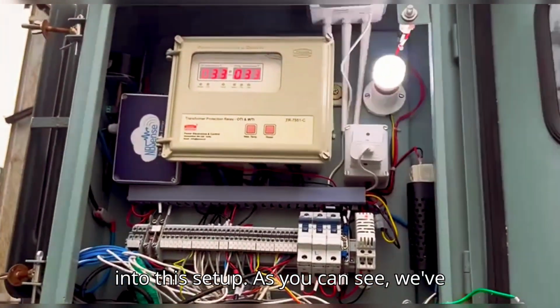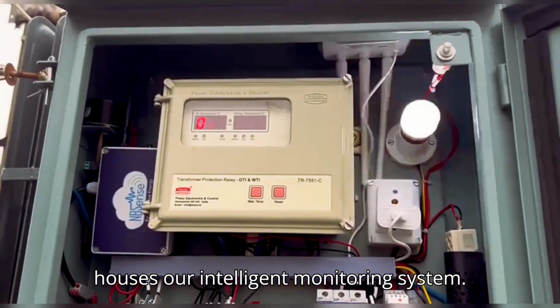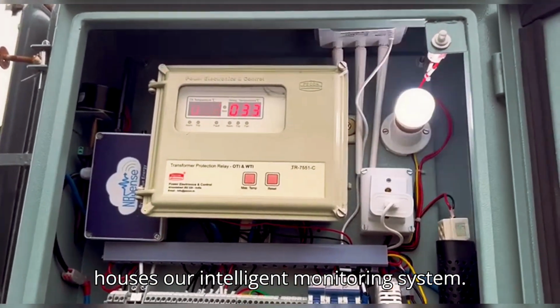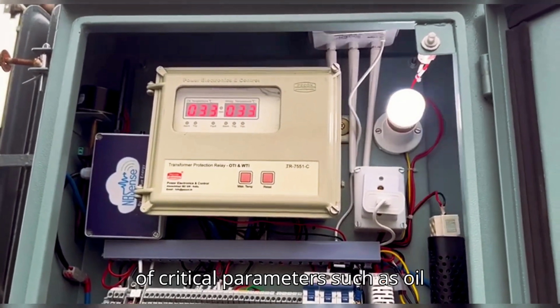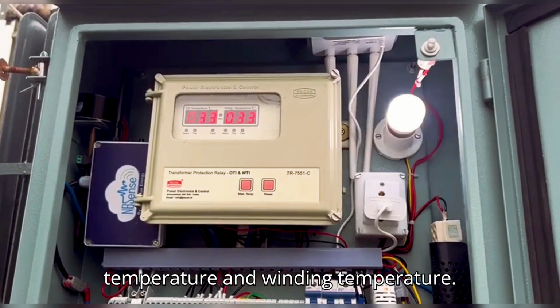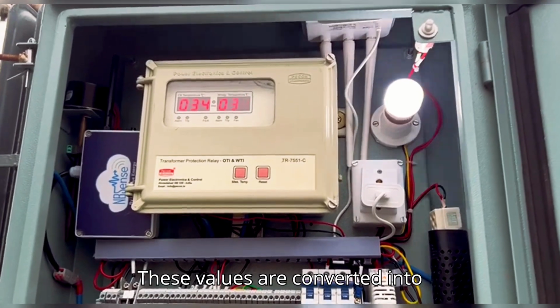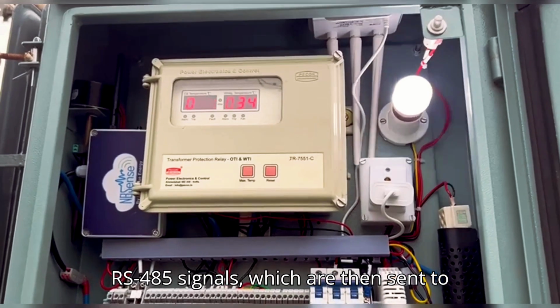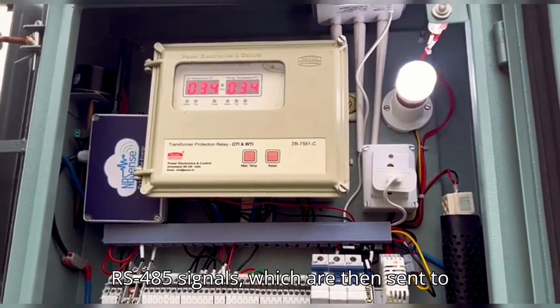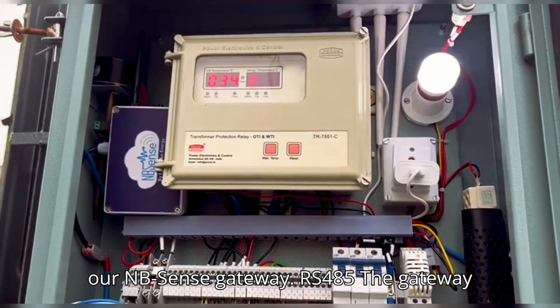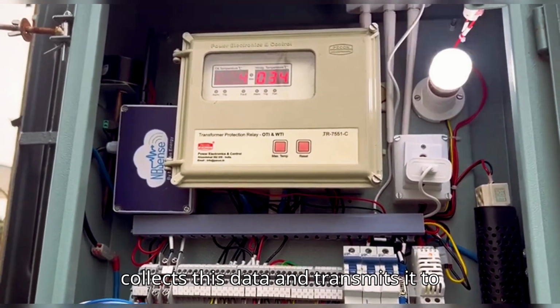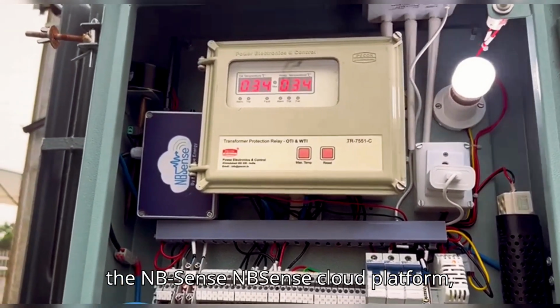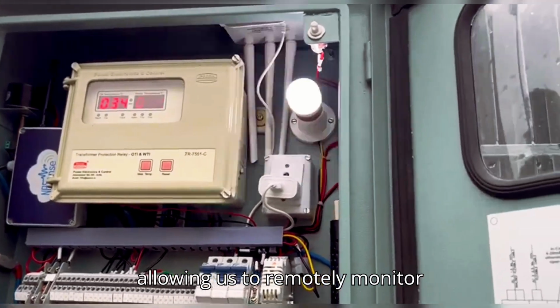As you can see, we've installed a marshalling box here. This unit houses our intelligent monitoring system. It keeps track of critical parameters such as oil temperature and winding temperature. These values are converted into RS485 signals, which are then sent to our NBSense gateway.